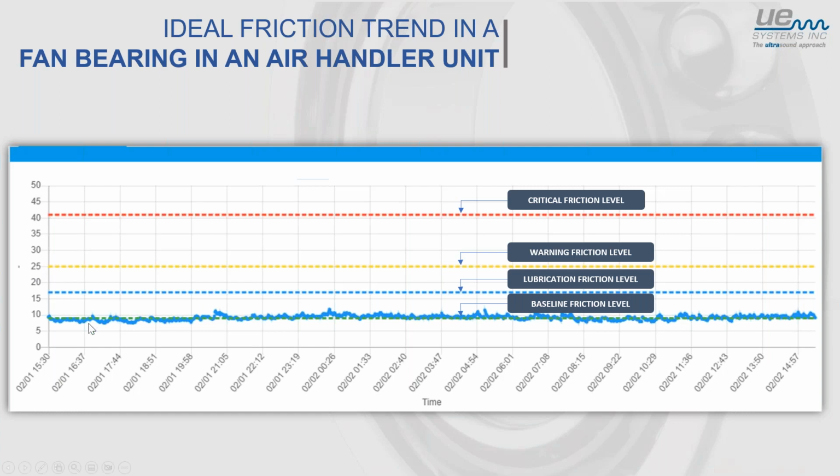That's fine, right? People ask me, well, what happens if the sensor fails? And with all electronics, eventually they will fail. Our mean time to failure is 10, 15 years plus. But when it does fail, it looks like a dead heartbeat, right? It's a flat line. If you ever see a perfect flat line, there's no way it's a bearing, even if that bearing was properly installed, properly lubricated, just babied its whole life, it still won't be a perfect flat line.